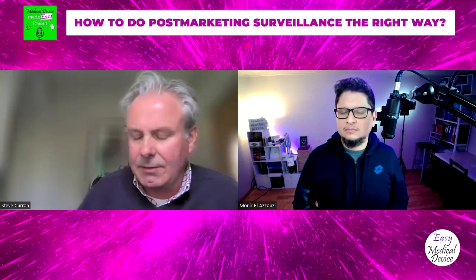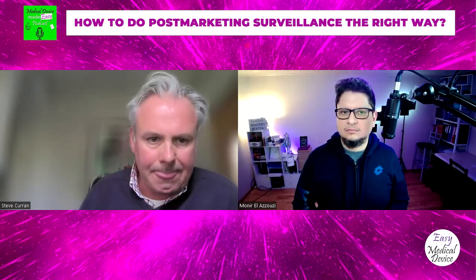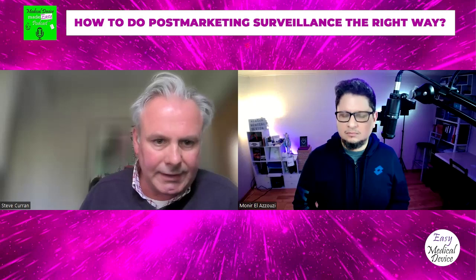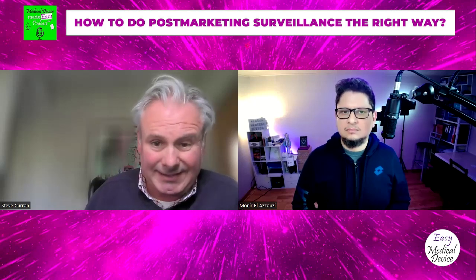Yeah, absolutely. Under the MDR now, you've got to write a periodic safety update report that needs to be put into your technical documentation, at least annually, and that will be reviewed very carefully by the notified bodies now. Again, if something comes out of vigilance, it might be reportable events, so you've got to report it to the competent authorities within all of the markets that you place your device on under MDR in the EU. You need to report to those competent authorities, and there are defined timescales for reporting, depending on the seriousness of the situation.